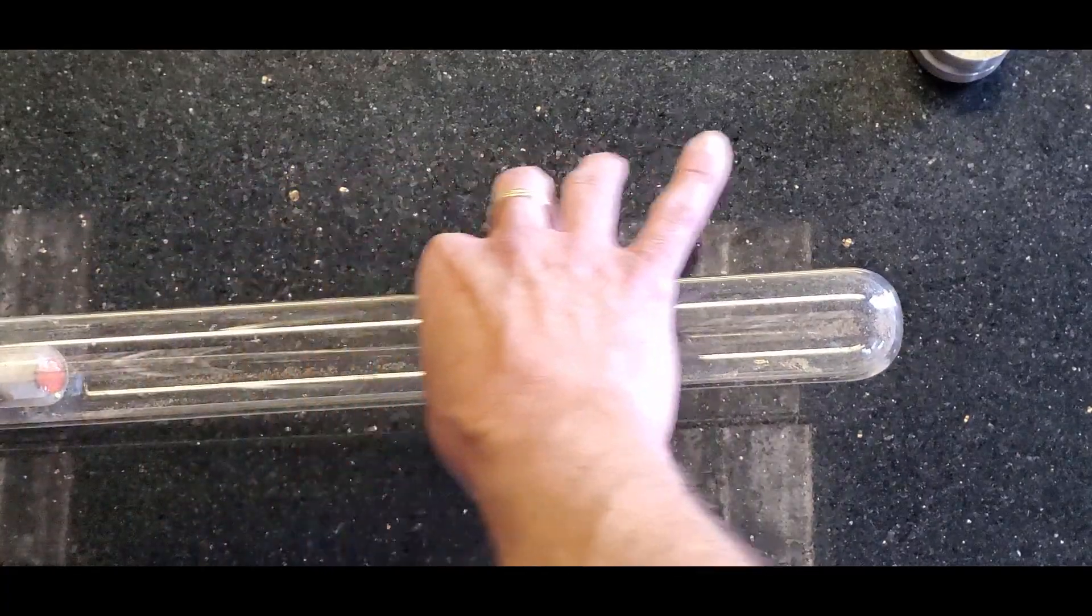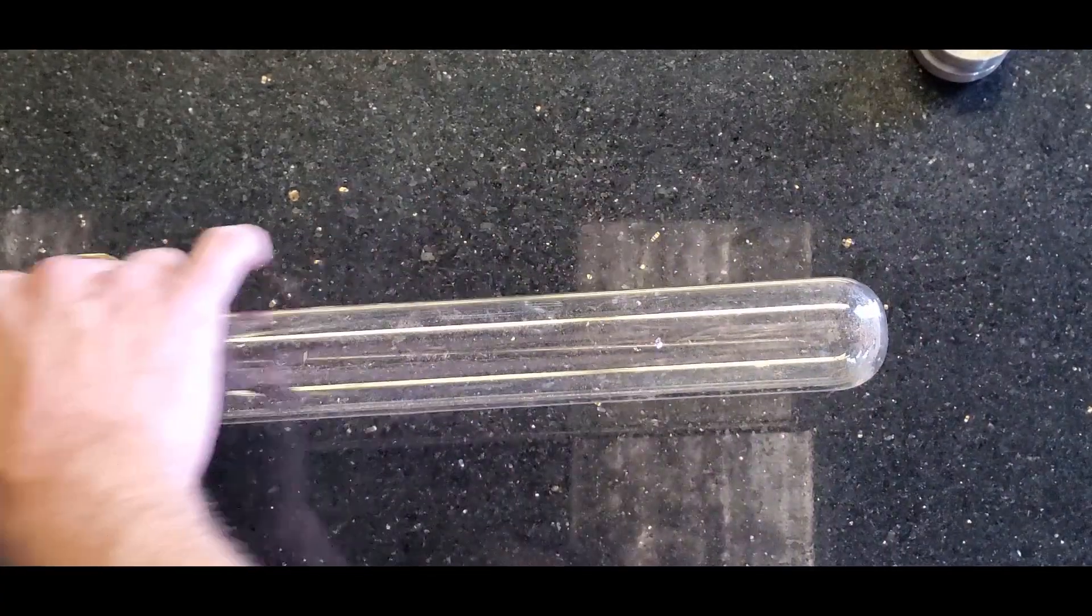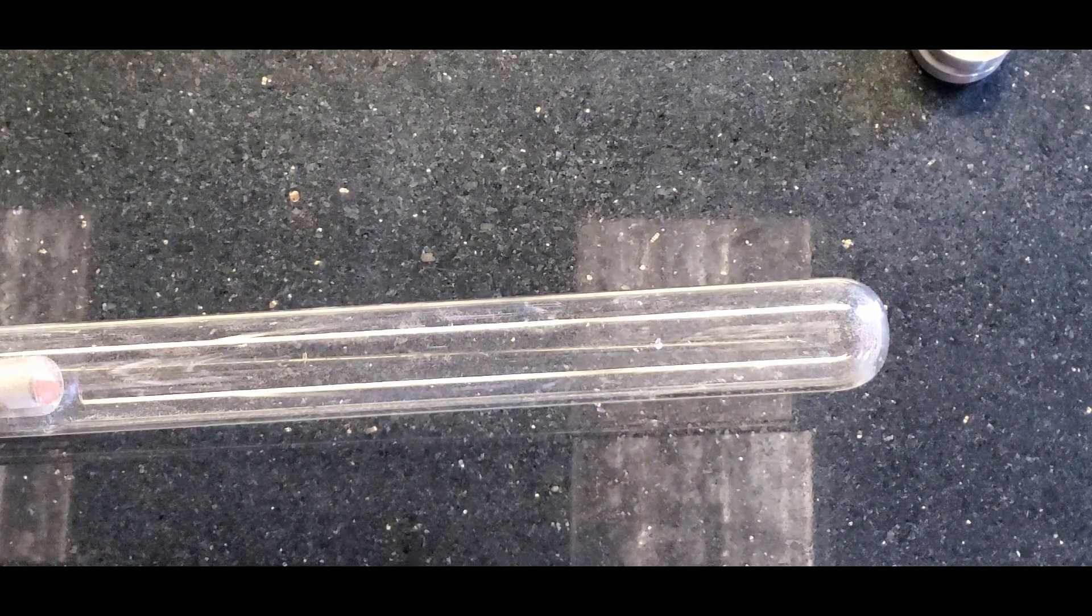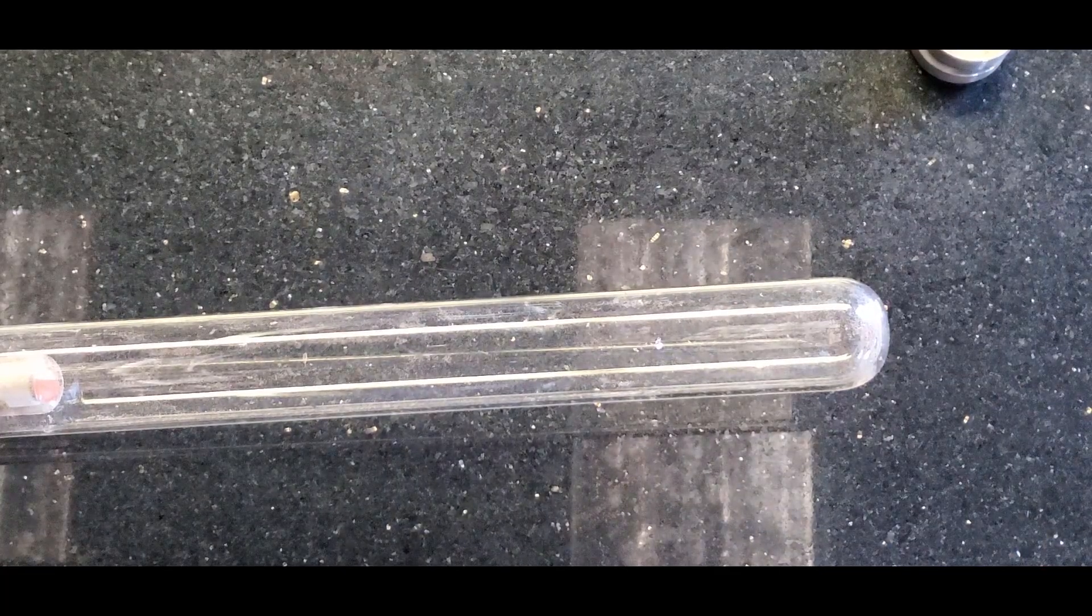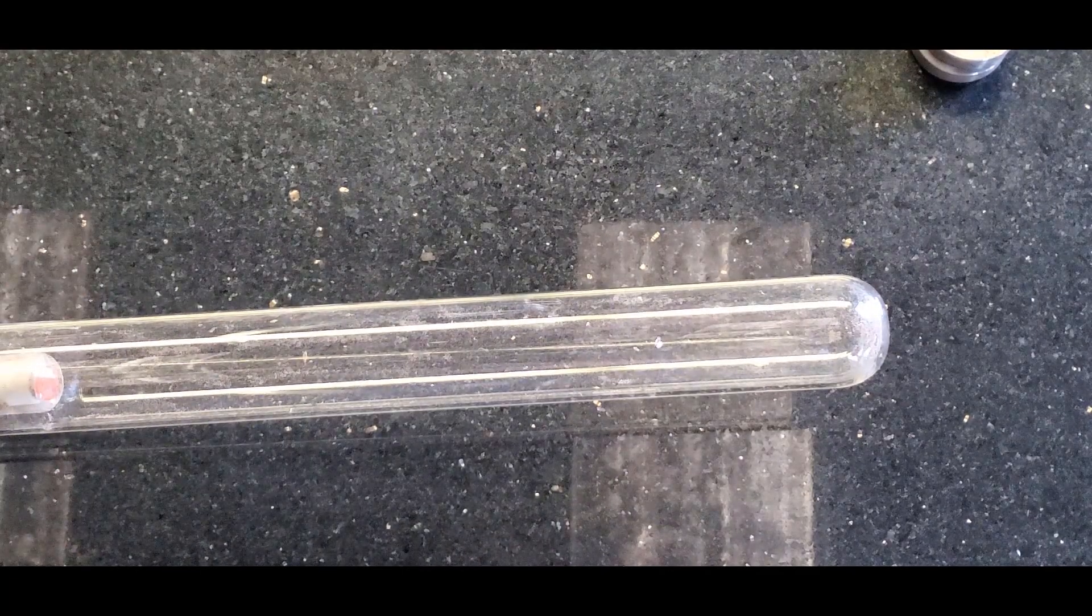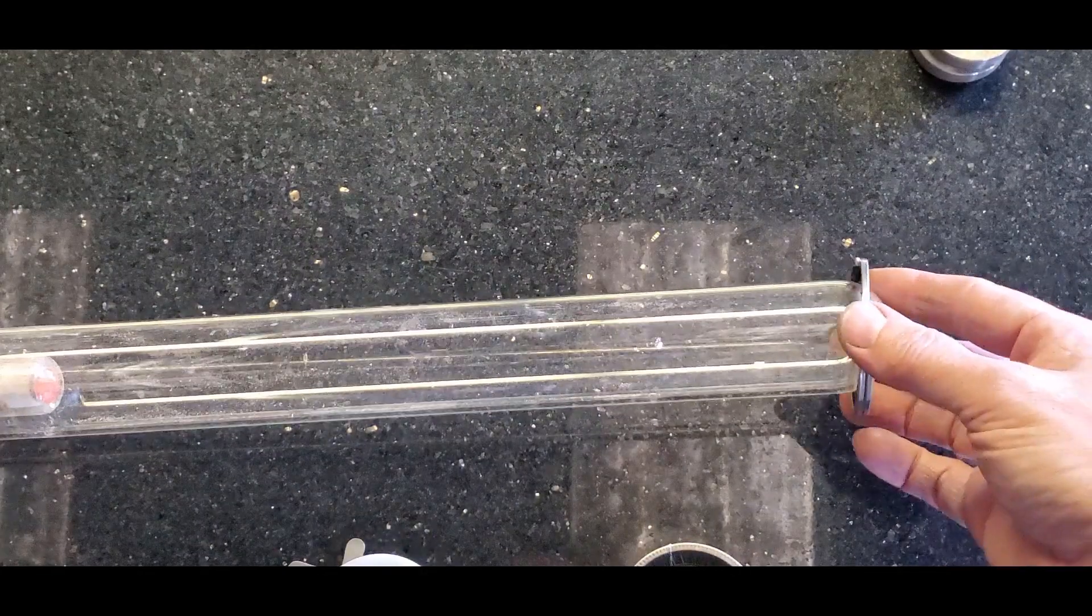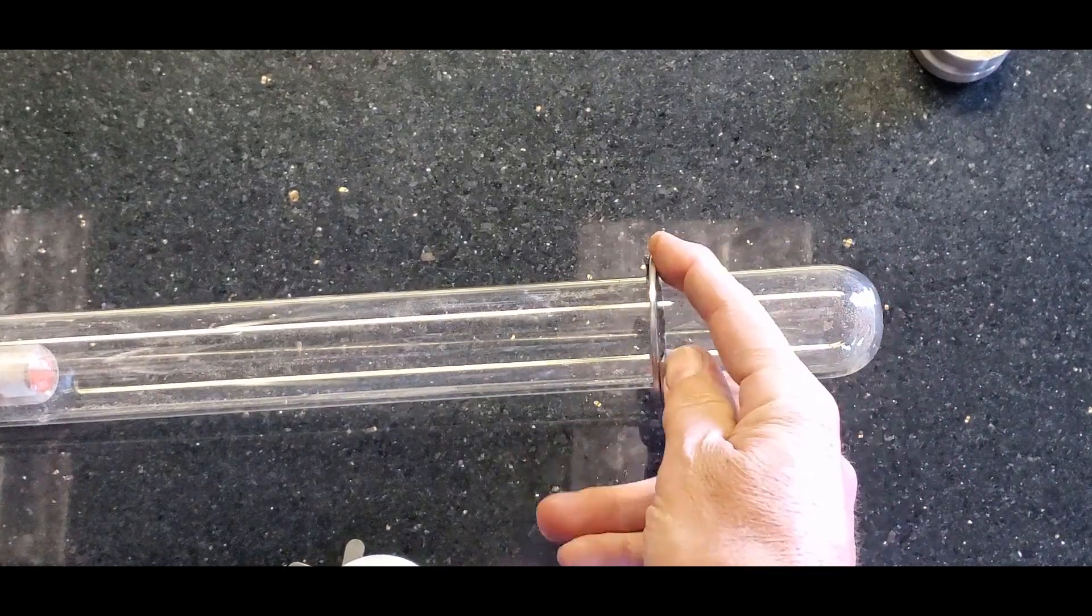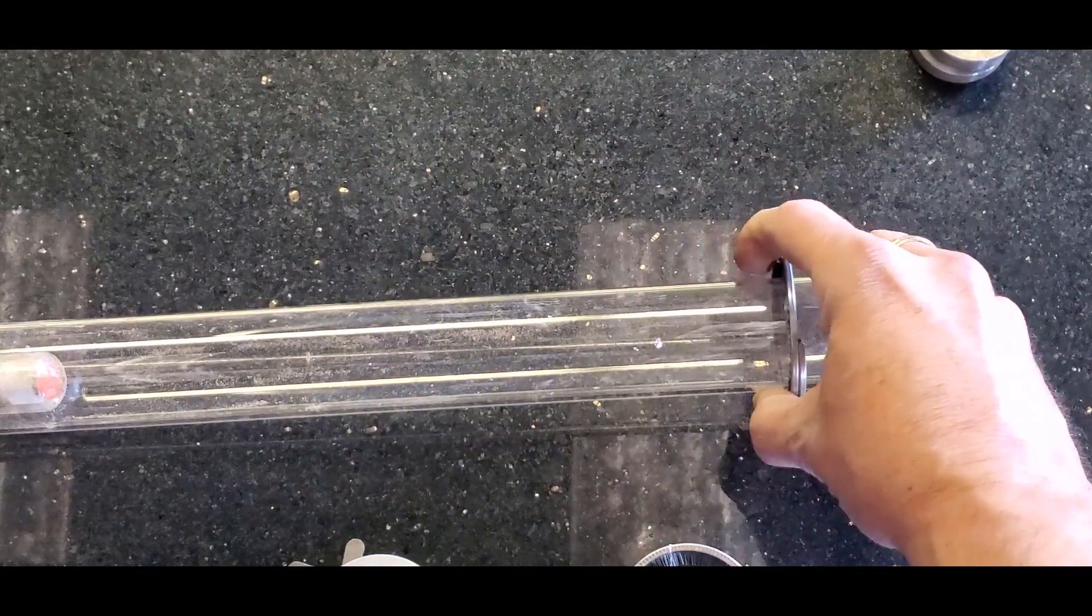This technology is mostly electrical, based around a NEMA 4X box which is stainless steel, and there's the array of tubes and there's a framework that goes down and holds the bottom ends of the tubes. In order to keep the quartz tubes clean you have to scrub them, and so there's a wiper plate that encapsulates all of the tubes and it pushes these bristle brushes up the tubes and then down the tubes. That takes a couple pounds of force to do it.